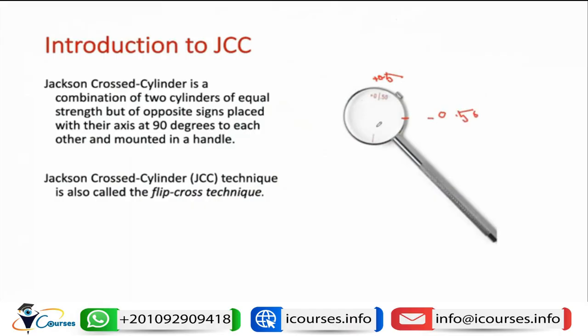So this is a spherocylindrical lens composed of two cylindrical lenses of equal power but of opposite signs and opposite direction to each other, and both of these lenses are mounted on a handle. By flipping this Jackson cross cylinder in front of the patient, we will be able to know what the axis is and what the accurate power is.